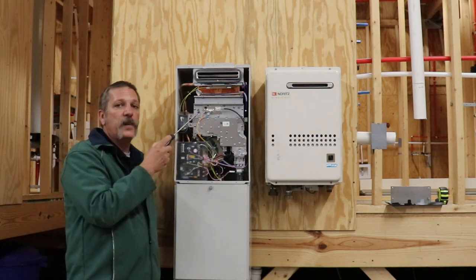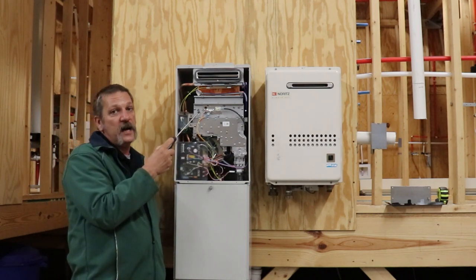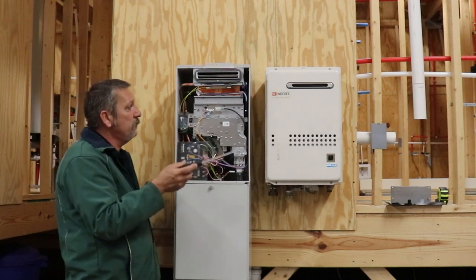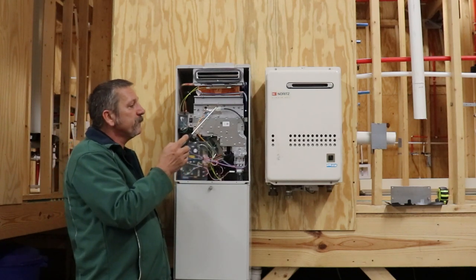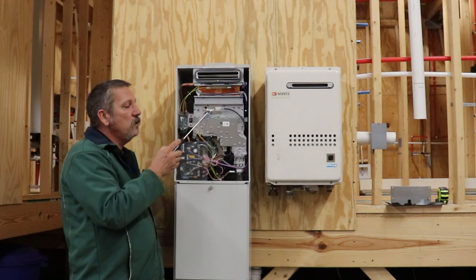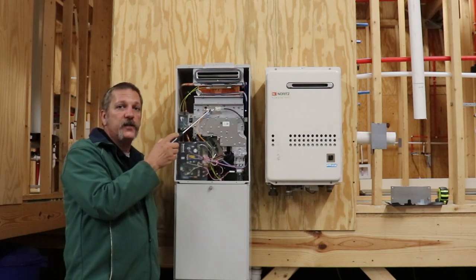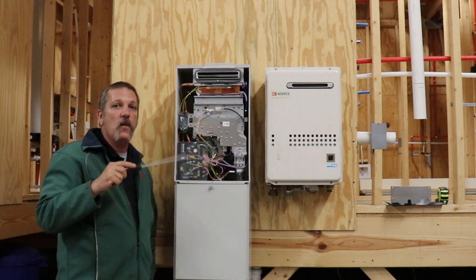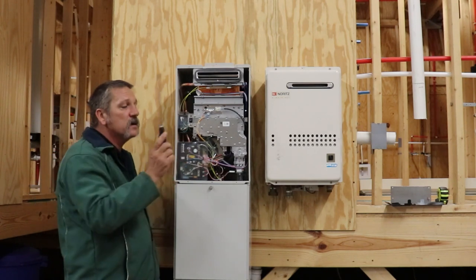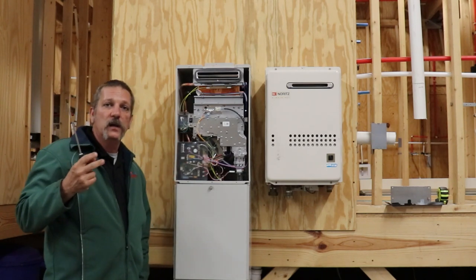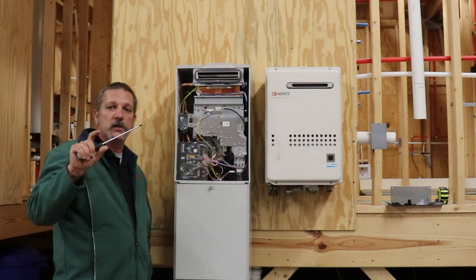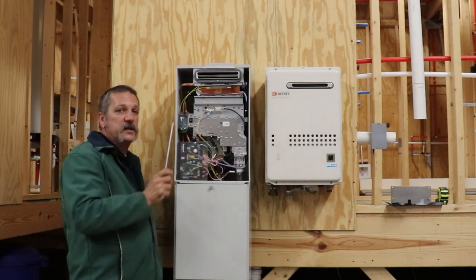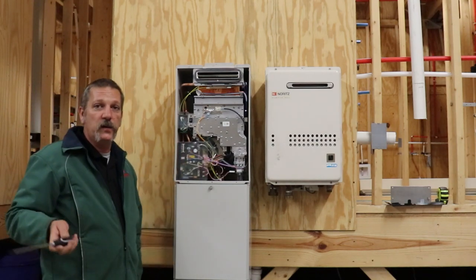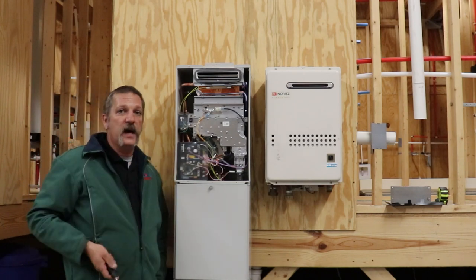Above that, you have your combustion chamber. Now, this is where the fire actually is. I like to call it flame box sometimes. You have an igniter, and you have your two flame rods, which are little rods that indicate whether it's burning or not. Now that igniter is like a charcoal grill, gas grill igniter. It just shoots a big old spark across there, and that's how it ignites. Now it's all electric, you don't have to do anything with it. It cuts on and does it itself.